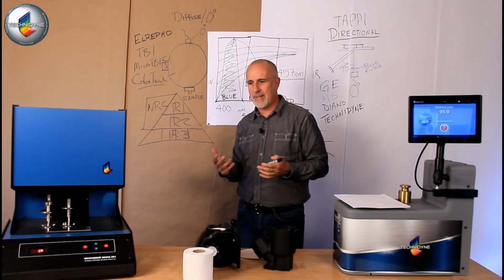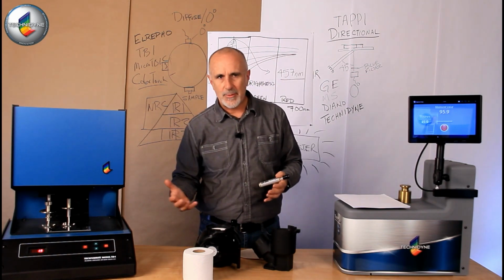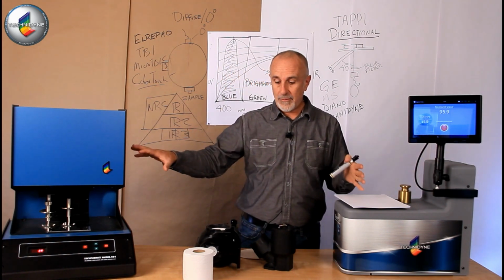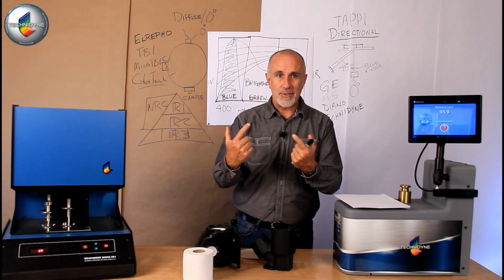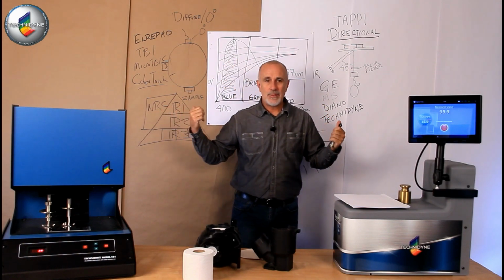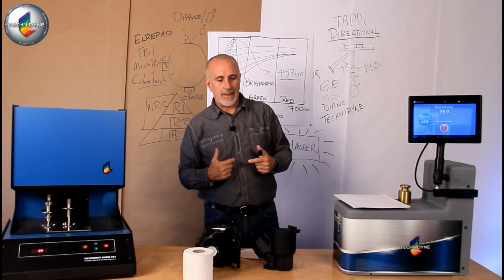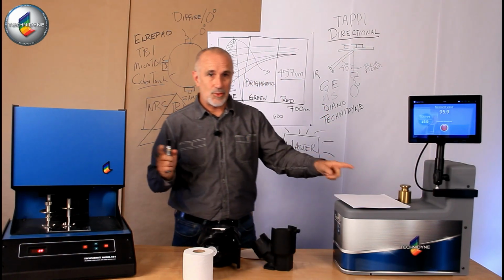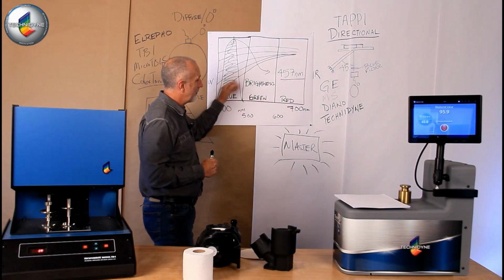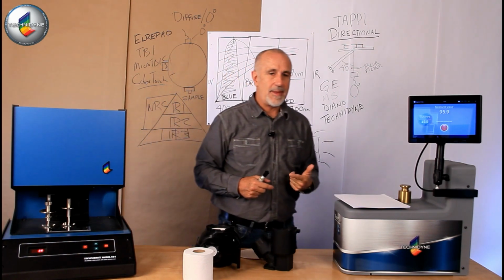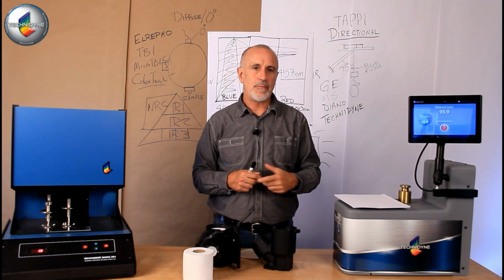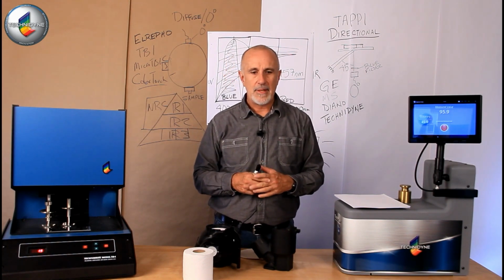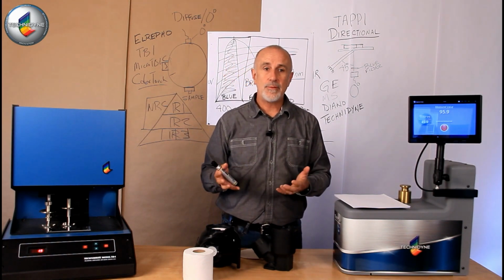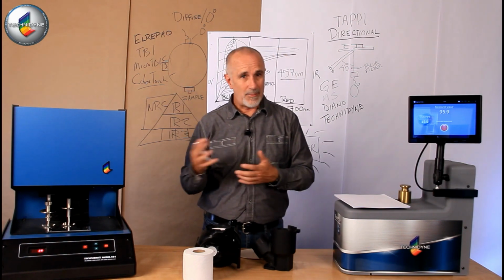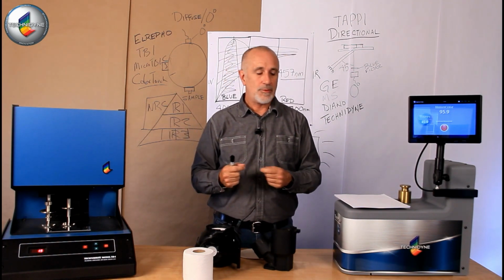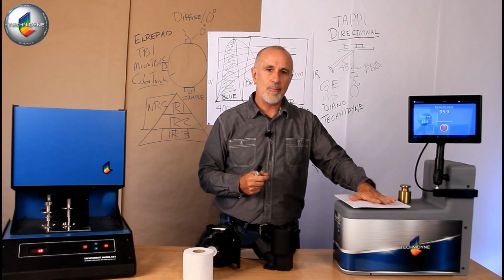So the two methods today, you've got the differences we've talked about already. The geometric differences are there. The photometric differences come in via the calibration point, and then the spectral response, again, is the same between the two. All right, so it's very important that calibration becomes part of your regular routine program. Paper standards are what we use because paper is what we make, and we don't want to use a transfer standard different from what we make.